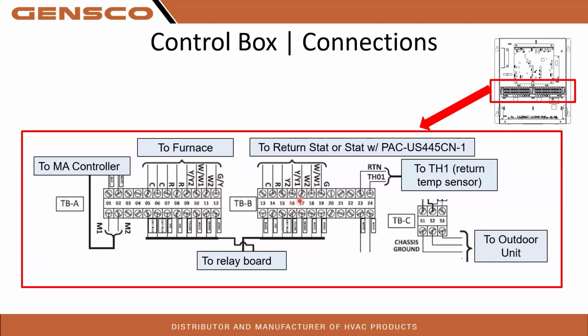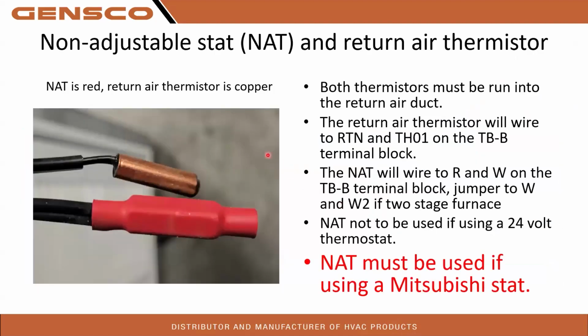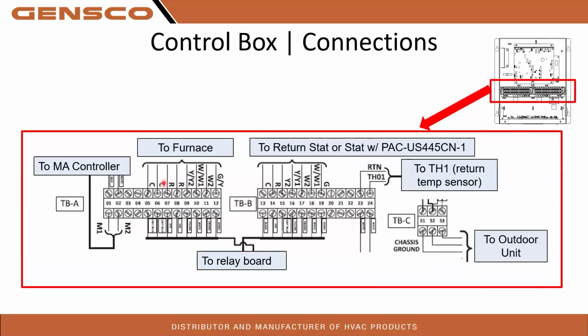Over here on the TBB block, this is for your 24-volt thermostat, or if you're not using that, the non-adjustable stat. I'll get to that a little bit more in a bit. But just like normal 24-volt controls: red, common, Y1, Y2, Y, W1, W2, and G. The return air thermistor plugs into RTN and TH01. That is all the way down here at the bottom of this block, far right-hand side. Non-adjustable stat and return air thermistor. So this is the return air thermistor. These both come in your kit. This return air thermistor is what's going to plug into RTN TH01 right here.